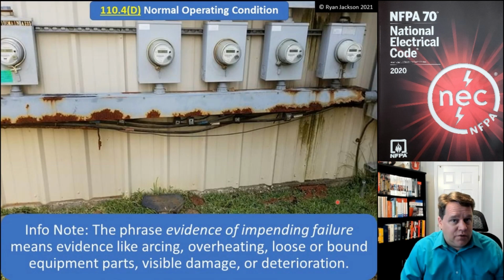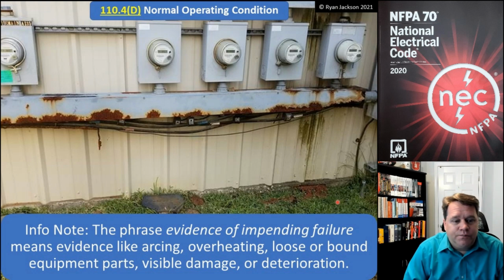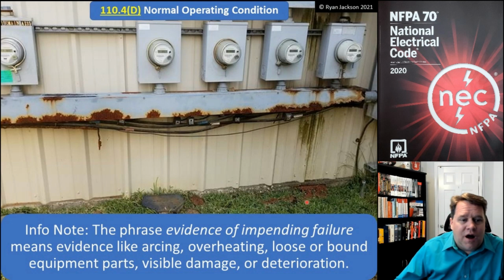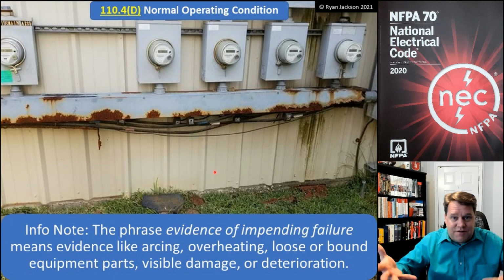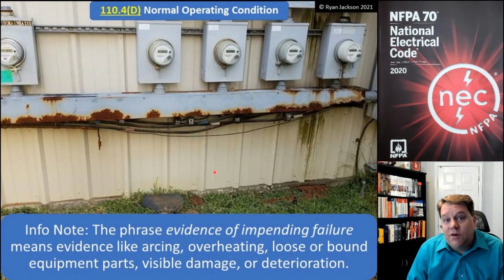And of course, we have a note that tells us what that means as well. Evidence of impending failure means evidence like arcing, overheating, loose or bound equipment parts, visible damage, deterioration, things like that. Is there any normal operation of this equipment? No. The bottom of the wireway is the little brown bits on the grass here, right? It's deteriorated down to nothing. There's no normal operation of this equipment. It's not in a normal operating condition.